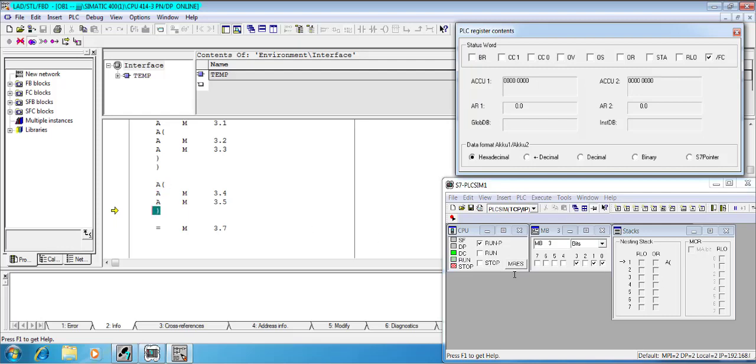So what it will actually do is that it will combine the value of the RLO that was previously here before execution of that instruction with the value that was yielded after execution of this second instruction. So RLO from here will be combined with RLO from here with an AND instruction, and because both of them are zeros, we expect the result of logic operation after execution of this instruction to be 0. And now, as you can see here, the entry was removed from our nesting stack.